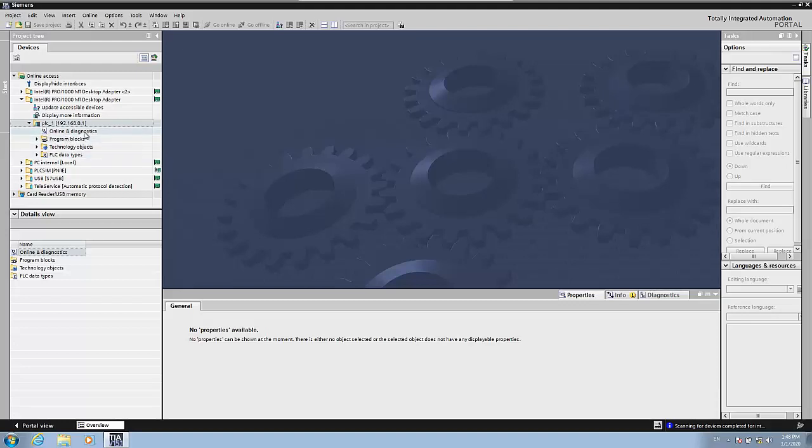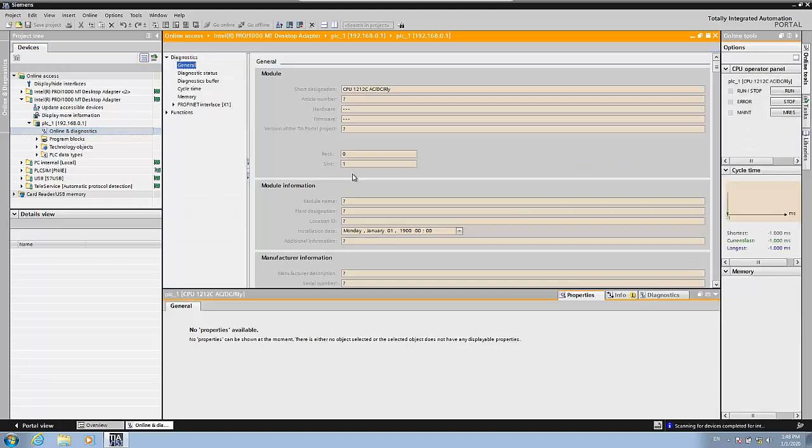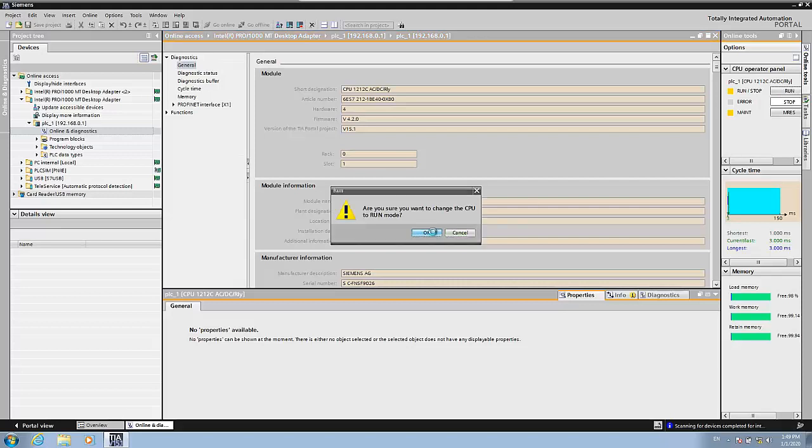Now I can click on online diagnostics to have the same view that I had in my previous video. There is something really important here. Look, in the operator panel, we have the PLC in stop mode. If I change it to run, I will not be able to change or modify the IP address.